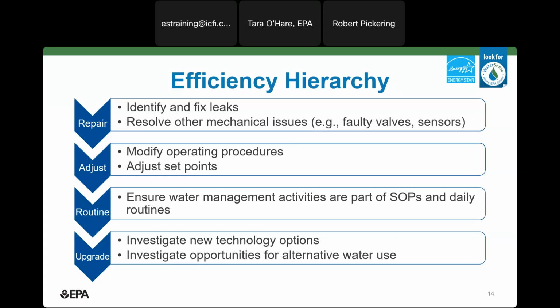Second, once everything is working as intended, you can then consider low and no cost adjustments to the system to achieve water efficiency. Oftentimes, there are easy opportunities to make simple adjustments to controls or operating procedures of a system that don't necessarily require a major investment. For example, for a cooling tower, it may be possible to change the settings on a conductivity controller so that it blows down less frequently while still operating within the acceptable range for the cooling tower.